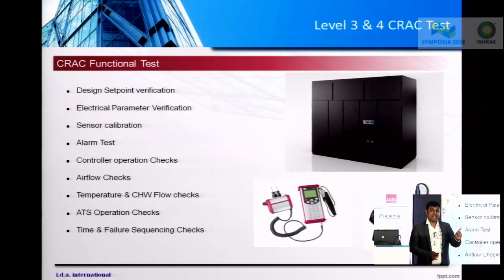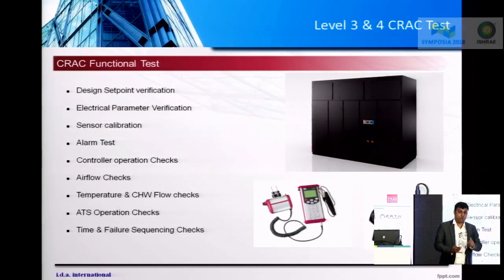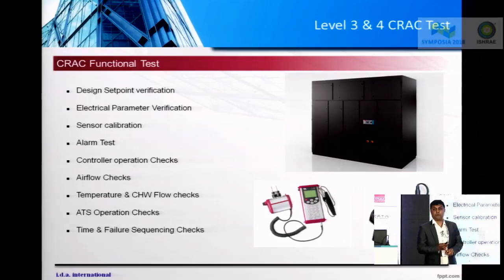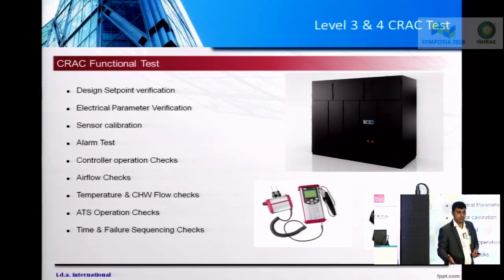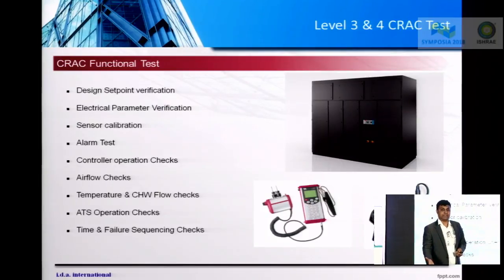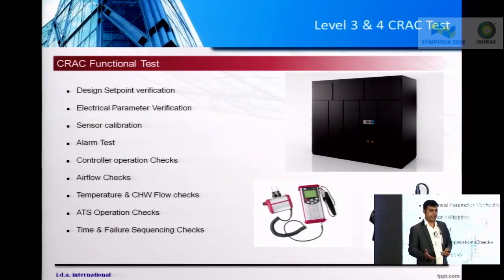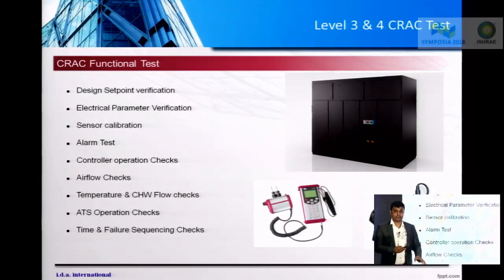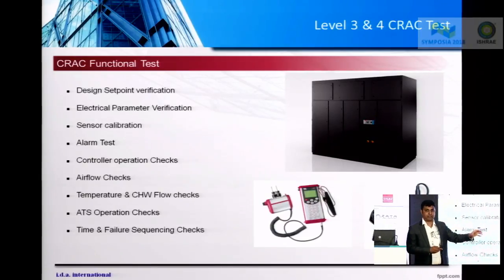The first thing is design set point verification. What are the set points you're putting for temperature, relative humidity, alarms for high temperature, low temperature, alarms for low humidity, high humidity. So you have to verify those design set points. The second part is electrical parameter verification. You have to ensure what's the power consumed by the compressor, by the fans, by the heaters, by the humidifiers. So you have to verify all these parameters as part of electrical parameter verification.